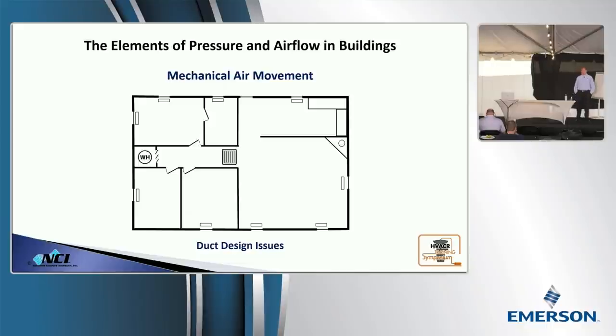Does this look like a standard house that some of you guys have to deal with? Let's say this is just a ranch, it could be on a slab, central return, water heater is located in a closet there on the left-hand side with a louvered door. Pretty standard install, right? So with all the doors open, and guys, this could be a perfectly tight duct system. Everything's great on this thing. It's balanced. The system is running pretty close to its laboratory rated capacity. You've done a rocking job.